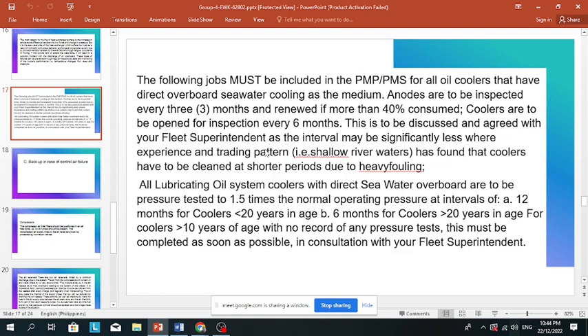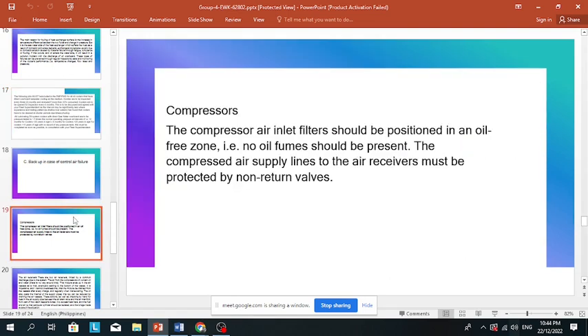Good day everyone. So, backup in case of control air failure. First is the compressors. The compressor air inlet filter should be positioned in an oil-free zone. No oil fumes should be present. The compressed air supply lines to the air receivers must be protected by non-return valves.